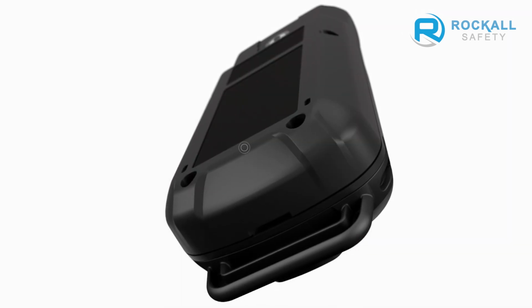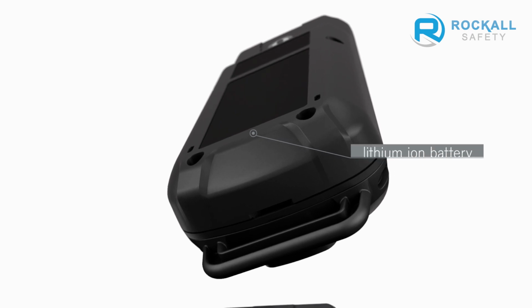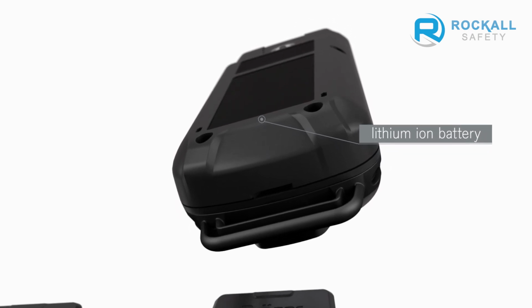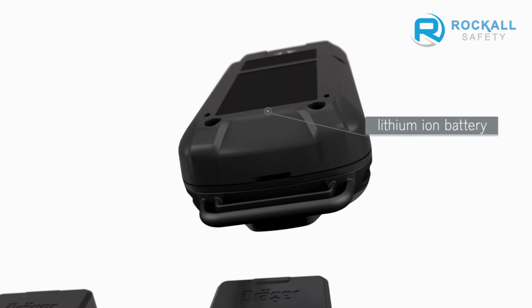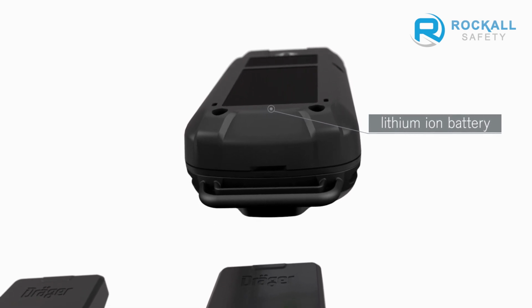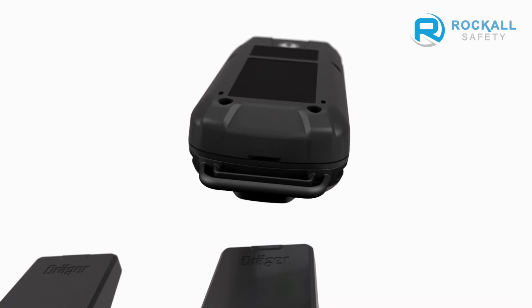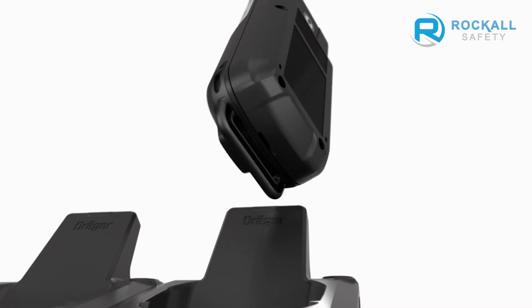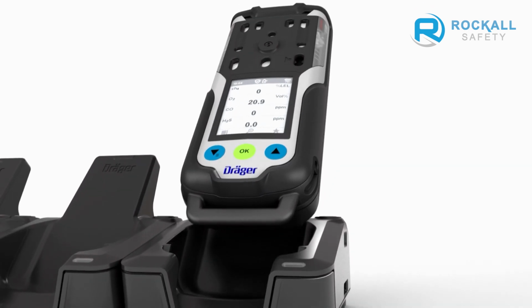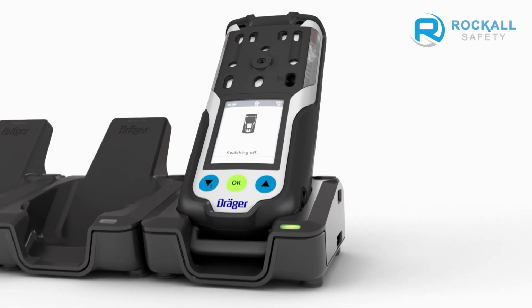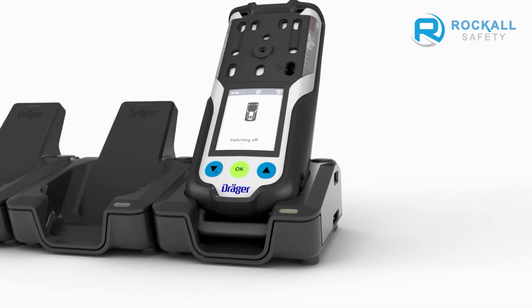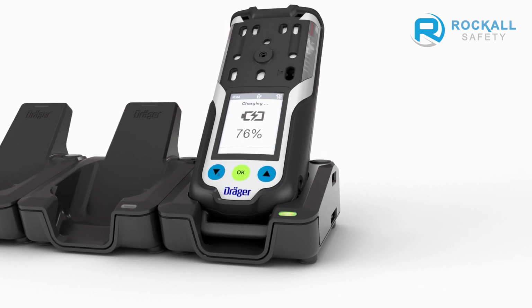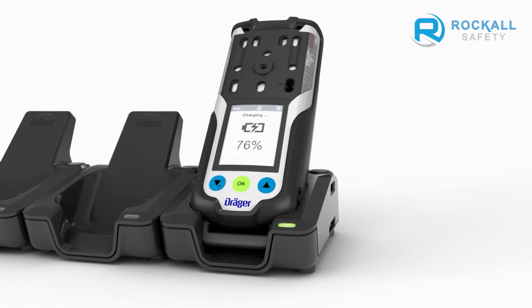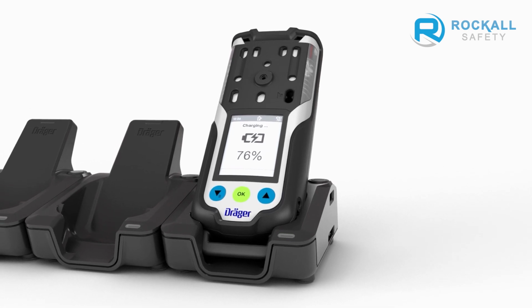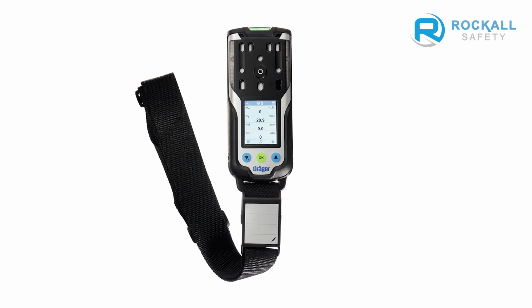The X-am 8000 is equipped with a rechargeable lithium-ion battery, which is charged inductively. Consequently, contaminations have no effect on the charging process and the contacts cannot become corroded. The gas detector switches off automatically as soon as it is placed in the charging cradle, and the green LED on the cradle starts to flash. After 8 hours of operation, the charging process takes approximately 4 hours. The battery is fully charged after 10 hours at the latest.